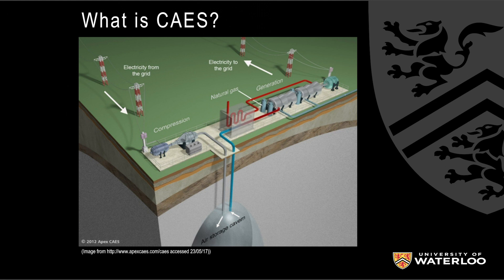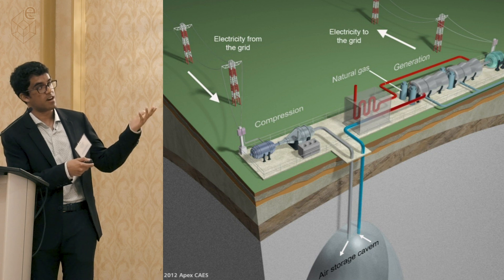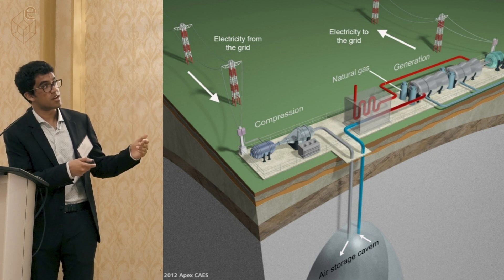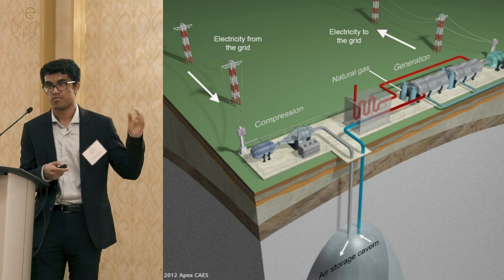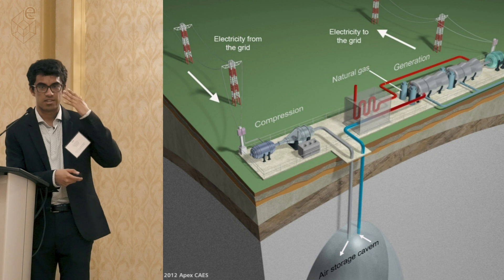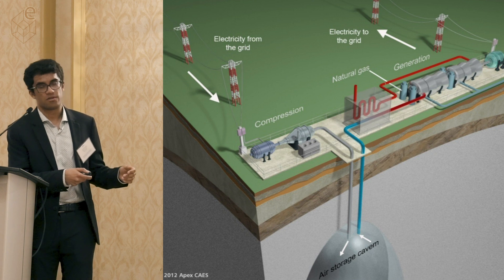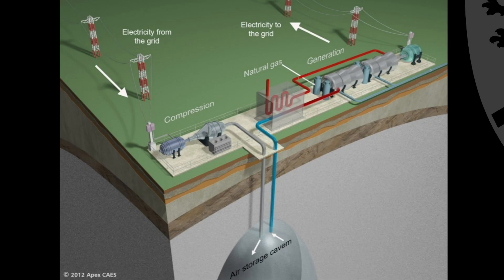What is CAES in practice? Compressed air energy storage involves taking electricity from the grid — perhaps during off-peak hours or from renewables — and using that electricity to drive an air compressor. We take ambient air, pressurize it, and send the pressurized air down to some form of vessel, such as a salt cavern, which I'd argue is the most prominent solution. When we want to harness power later, we simply release a valve, allow pressurized air to travel through a generator, and the force of the air from compression to expansion drives the turbine to produce electricity for the grid.